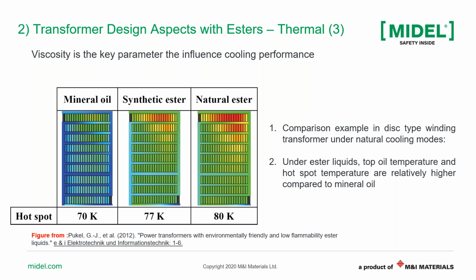One is simulation, one is the practical aspect of what we expect of the temperature difference between mineral oil and synthetic ester. So in this slide, you can see an example from a published paper. The reference is below. And here we're using computational fluid dynamics, CFD, to really estimate the flow distribution within a disk type transformer and the temperature distribution.